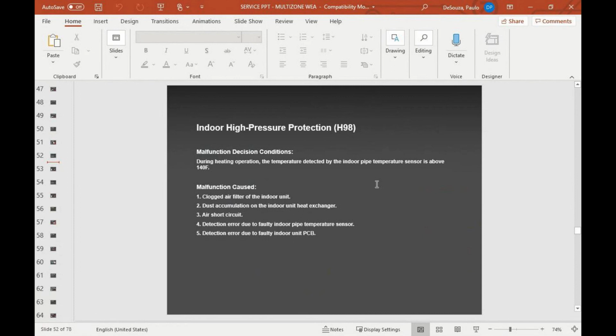H97, very common winter time. Winter time, H97, I already got, I can say, maybe 3 calls so far since October, November last year till today. H97 snowstorm. Definitely when there is a snowstorm, the next day I get this error code. I tell them go outside and check the outdoor unit, fully covered with snow. So always remember, tell the homeowner, treat this outdoor unit like your driveway. You got to shovel snow. You got to dust and remove the snow. Clean it. Be part of that unit. You know, it will give you good service. It will last forever.